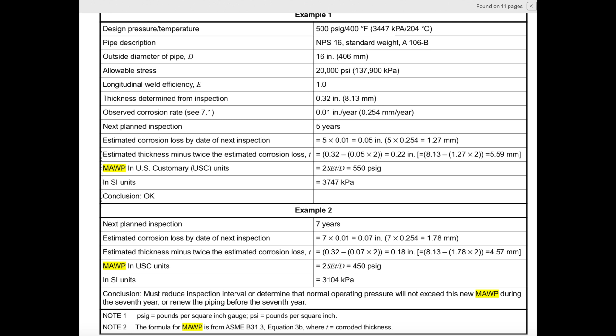Here, the required thickness determination. The required thickness of a pipe shall be the greater of the pressure design thickness or the structural minimum thickness. For services with high risk, the piping engineer should consider increasing the required thickness to provide for anticipated or unknown loadings. Or the piping engineer will decide, or the inspection person will decide, which to be considered, whether pressure design thickness or the structural minimum thickness.